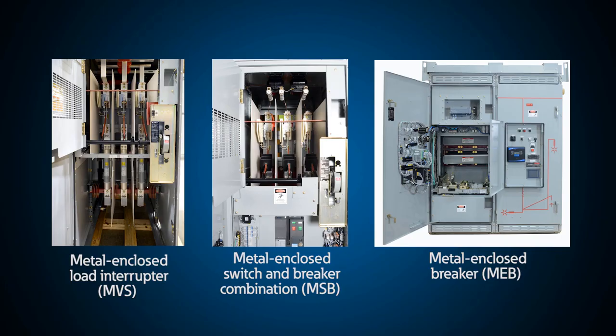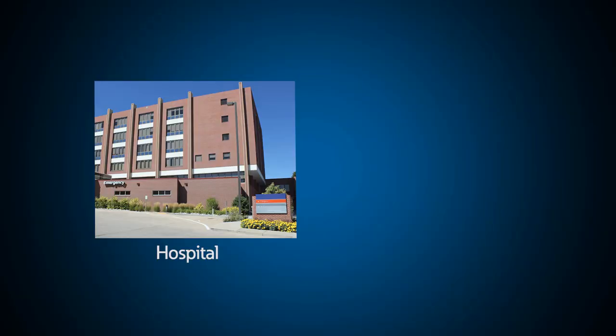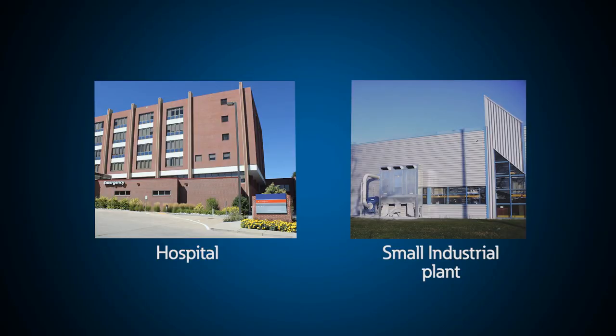Metal-enclosed switchgear contains circuit protection devices including circuit breakers, power fuses, and fusible switches, as well as control and metering equipment. These devices can be fixed-mounted in common compartments and do not require the separate barriers or compartmentalization required in metal-clad switchgear. Metal-enclosed switchgear is applied in commercial and many industrial facilities where the rugged construction of metal-clad may not be required.